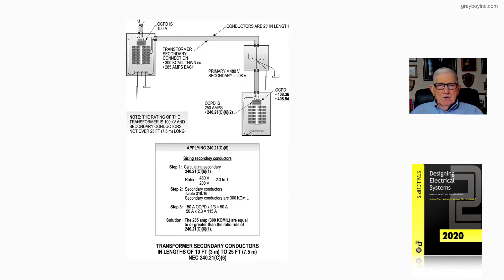So the note tells us in the illustration, the rating of the transformer is 100kVA, and the secondary conductors are not over 25 foot, but they're over 10 foot. So we have a 250 amp overcurrent device in the panel board, and we're complying with 408.36.